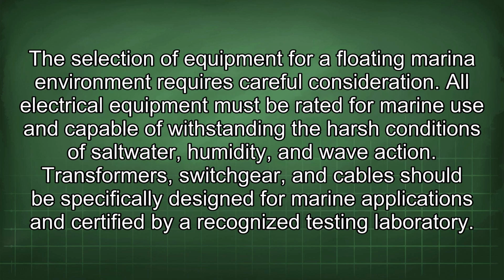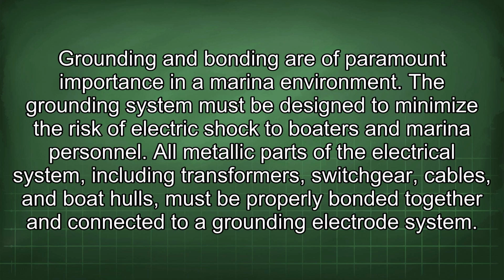The selection of equipment for a floating marina environment requires careful consideration. All electrical equipment must be rated for marine use and capable of withstanding the harsh conditions of saltwater, humidity, and wave action. Transformers, switchgear, and cables should be specifically designed for marine applications and certified by a recognized testing laboratory. Grounding and bonding are of paramount importance in a marina environment. The grounding system must be designed to minimize the risk of electric shock to boaters and marina personnel. All metallic parts of the electrical system, including transformers, switchgear, cables, and boat hulls, must be properly bonded together and connected to a grounding electrode system.